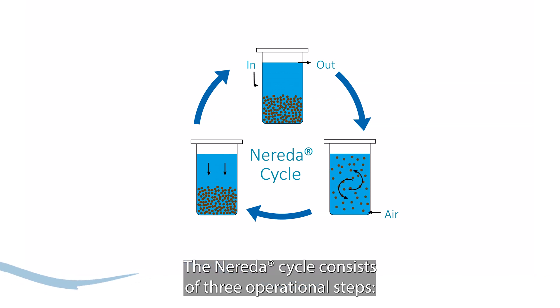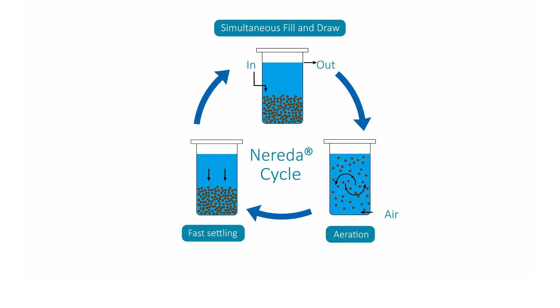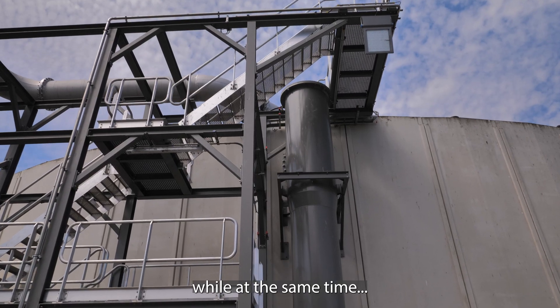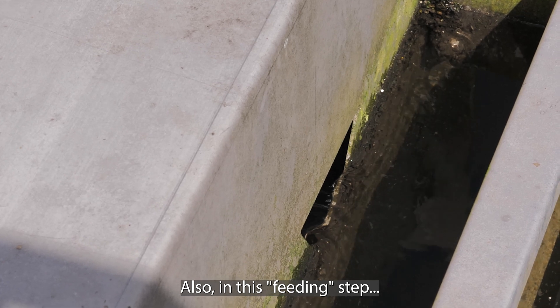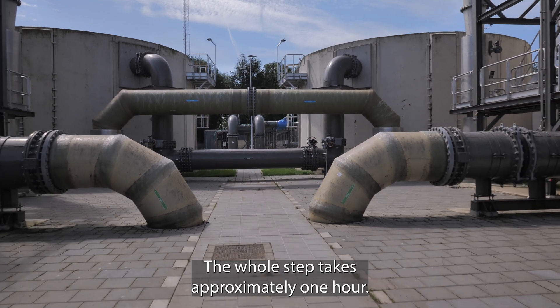The Nereda cycle consists of three operational steps: feed, aeration, and settling. In the first feed step, influent is fed to the bottom of the reactor, while at the same time the effluent is decanted from the top of the reactor — hence the term 'fill and draw.' Also in this feeding step, phosphorus is temporarily released. The whole step takes approximately one hour.